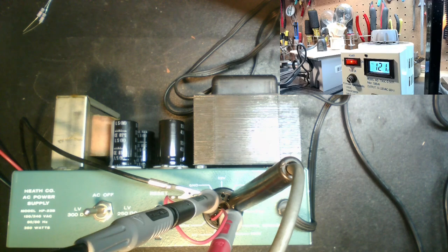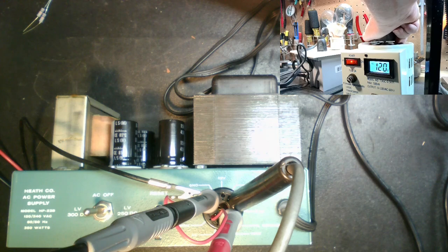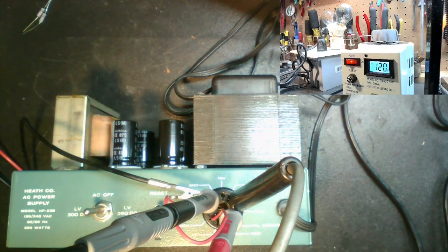Since I'm not seeing anything drawing excessive current, I'm going to bypass and give it full voltage. I'll set this right at 120 and bypass the bulbs. That brings us up to about 775, 780 on the high voltage, and 354 on the low voltage, which is good.